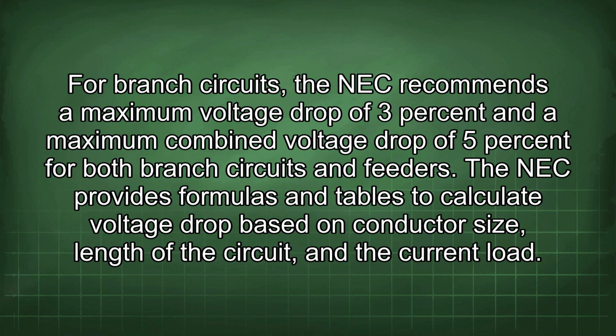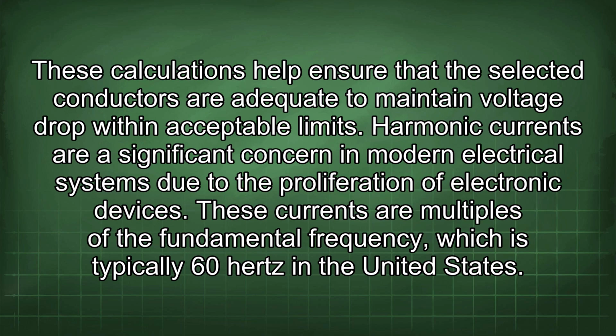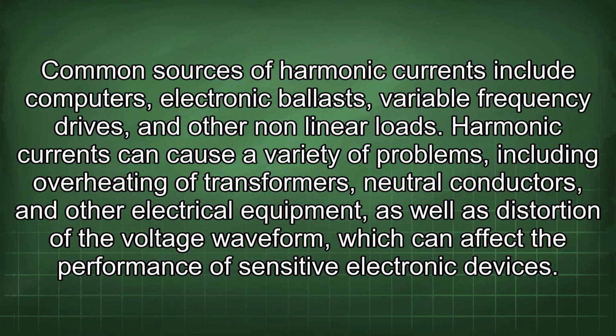The NEC provides formulas and tables to calculate voltage drop based on conductor size, length of the circuit, and the current load. These calculations help ensure that the selected conductors are adequate to maintain voltage drop within acceptable limits. Harmonic currents are a significant concern in modern electrical systems due to the proliferation of electronic devices. These currents are multiples of the fundamental frequency, which is typically 60 Hz in the United States. Common sources of harmonic currents include computers, electronic ballasts, variable frequency drives, and other nonlinear loads.